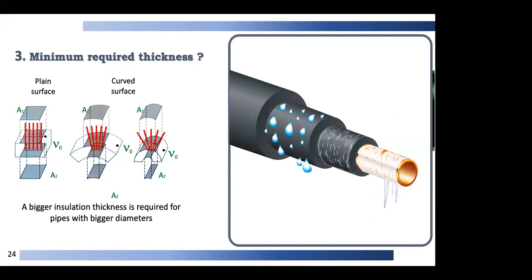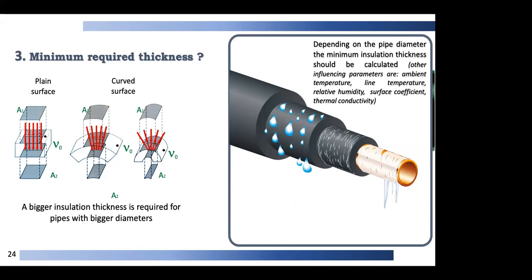A copper pipe without insulation shows freezing. With minimal thickness there is still condensation, but once a proper thickness is applied, there is no condensation on the pipe. Depending on the pipe diameter, the minimum insulation thickness should be calculated. Other influencing parameters include ambient temperature, line temperature, humidity, surface coefficient and thermal conductivity of the insulation.